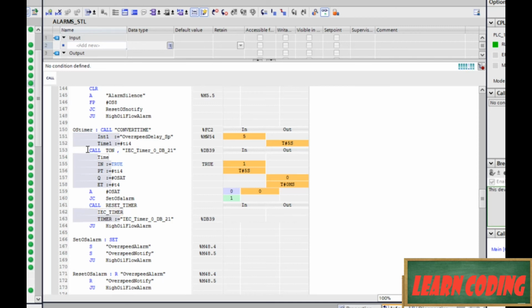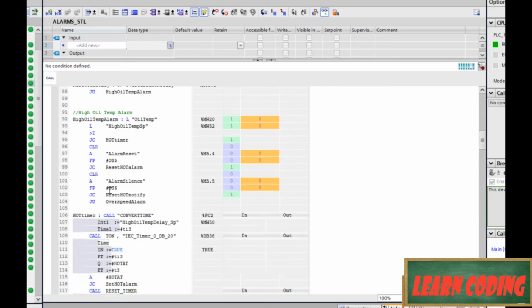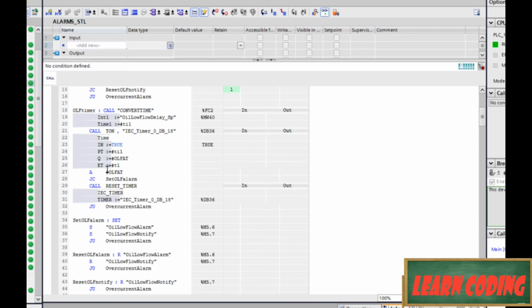What happens is we run through our timer logic, and anytime our timer has not completely timed out, we're resetting it. So basically, whether our timer is at 0, or starts timing, or is not timing, it's always resetting. So yeah, that's where I screwed up right there. So what I need to do is relocate this reset somewhere else. Let's go ahead and cut that out of here.